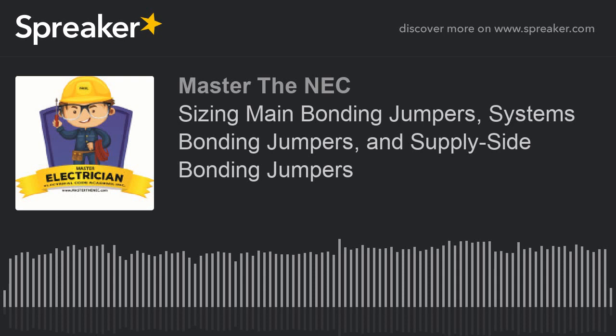All right, now, getting back to what we're talking about, main bonding jumper. So the first thing we want to know is, where do we go to give us the general rules for a main bonding jumper? In the National Electrical Code, we're going to look at 250.28. Now, 250.28 is titled Main Bonding Jumper and System Bonding Jumper. Why? Because they both serve identical functions, just in different sources. One dealing with the utility, and the other dealing with something like a separately derived system, whether it's a generator, if it's truly separately derived. That's a whole other episode we probably should do on why some are and some aren't. But also transformers, for example. So the sizing of the main bonding jumper or the system bonding jumper is very similar, and they utilize the same table within the National Electrical Code, which is 250.102(C)(1). And we'll talk about that in a minute.